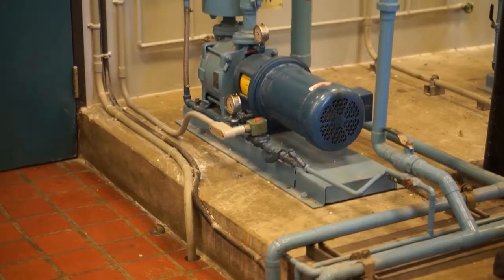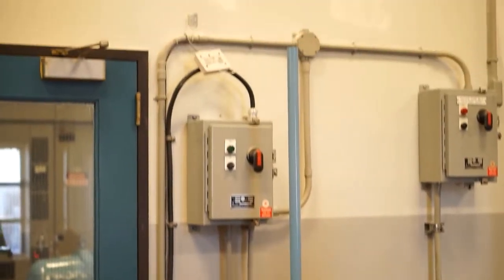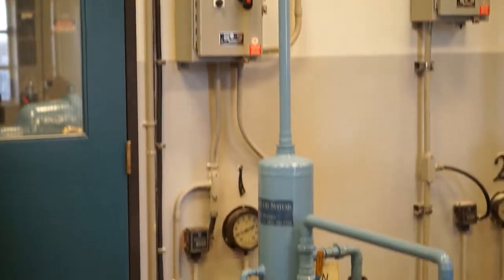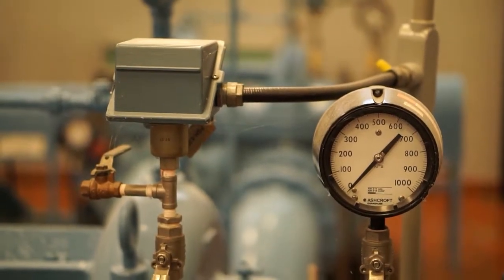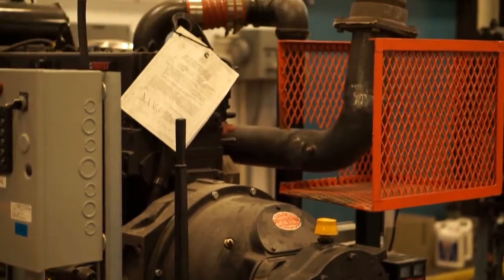Once the vacuum pumps have primed a high lift or low lift pump, the pumps are ready, filled with water at vacuum pressure. A good analogy is to think of a straw filled with water with your thumb over it. You don't need to do anything to maintain the volume. If there is any leakage in the system, then the vacuum pumps turn on for a few minutes to return the system back to its negative pressure setting.